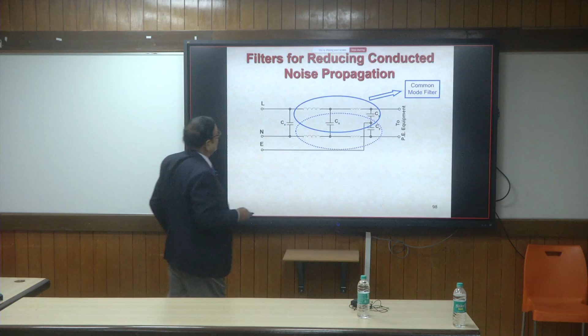You can integrate the common mode filter and differential mode filter into a common structure—don't confuse this with just a common mode filter; it's a particular integrated magnetic structure. Most large power applications use discrete differential mode and common mode filters separately. The advantage of the integrated structure is that the ampere-turns created by one winding are cancelled by the ampere-turns of the other, since current enters the dot on one side and flows out of the dot on the other. So the core does not see the main load ampere-turns—that flux is cancelled, and your core size is reduced.